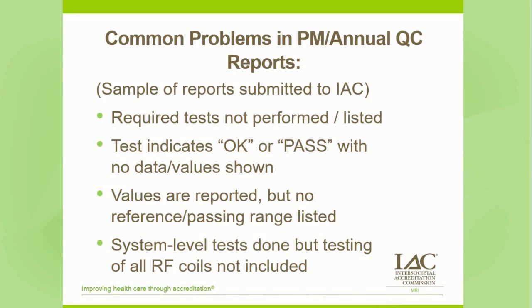We'll see just an 'okay' or a 'pass,' or we'll see a value like 129, but no indication of whether 129 is good, great, or terrible. And in looking at the individual RF coils — because those are the key interface for the signal coming from the patient getting into the system — we need to have all system-level tests, but it is quite frequent that we see a report addressing system-level maintenance and performance with no indication of performance checks or visual inspections for each individual coil. Because those are a critical link in the chain, we really do need to see that all coils are being evaluated and, where appropriate, being serviced.